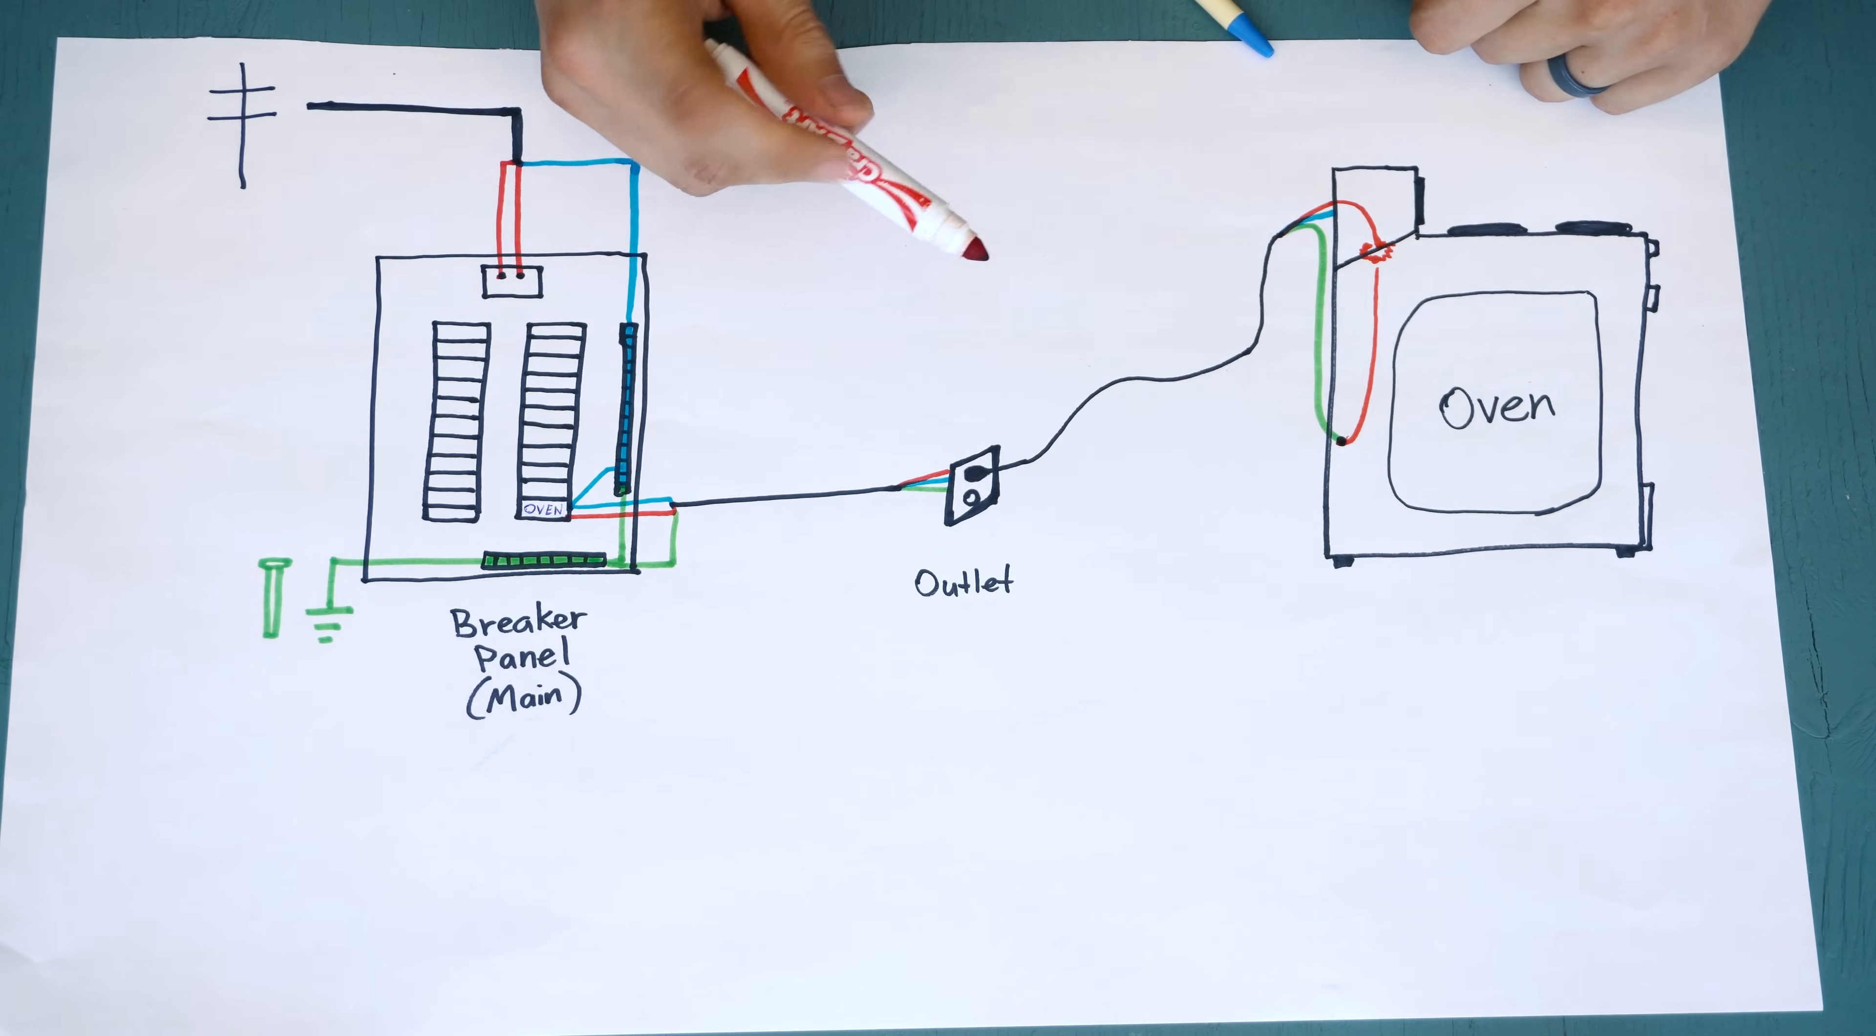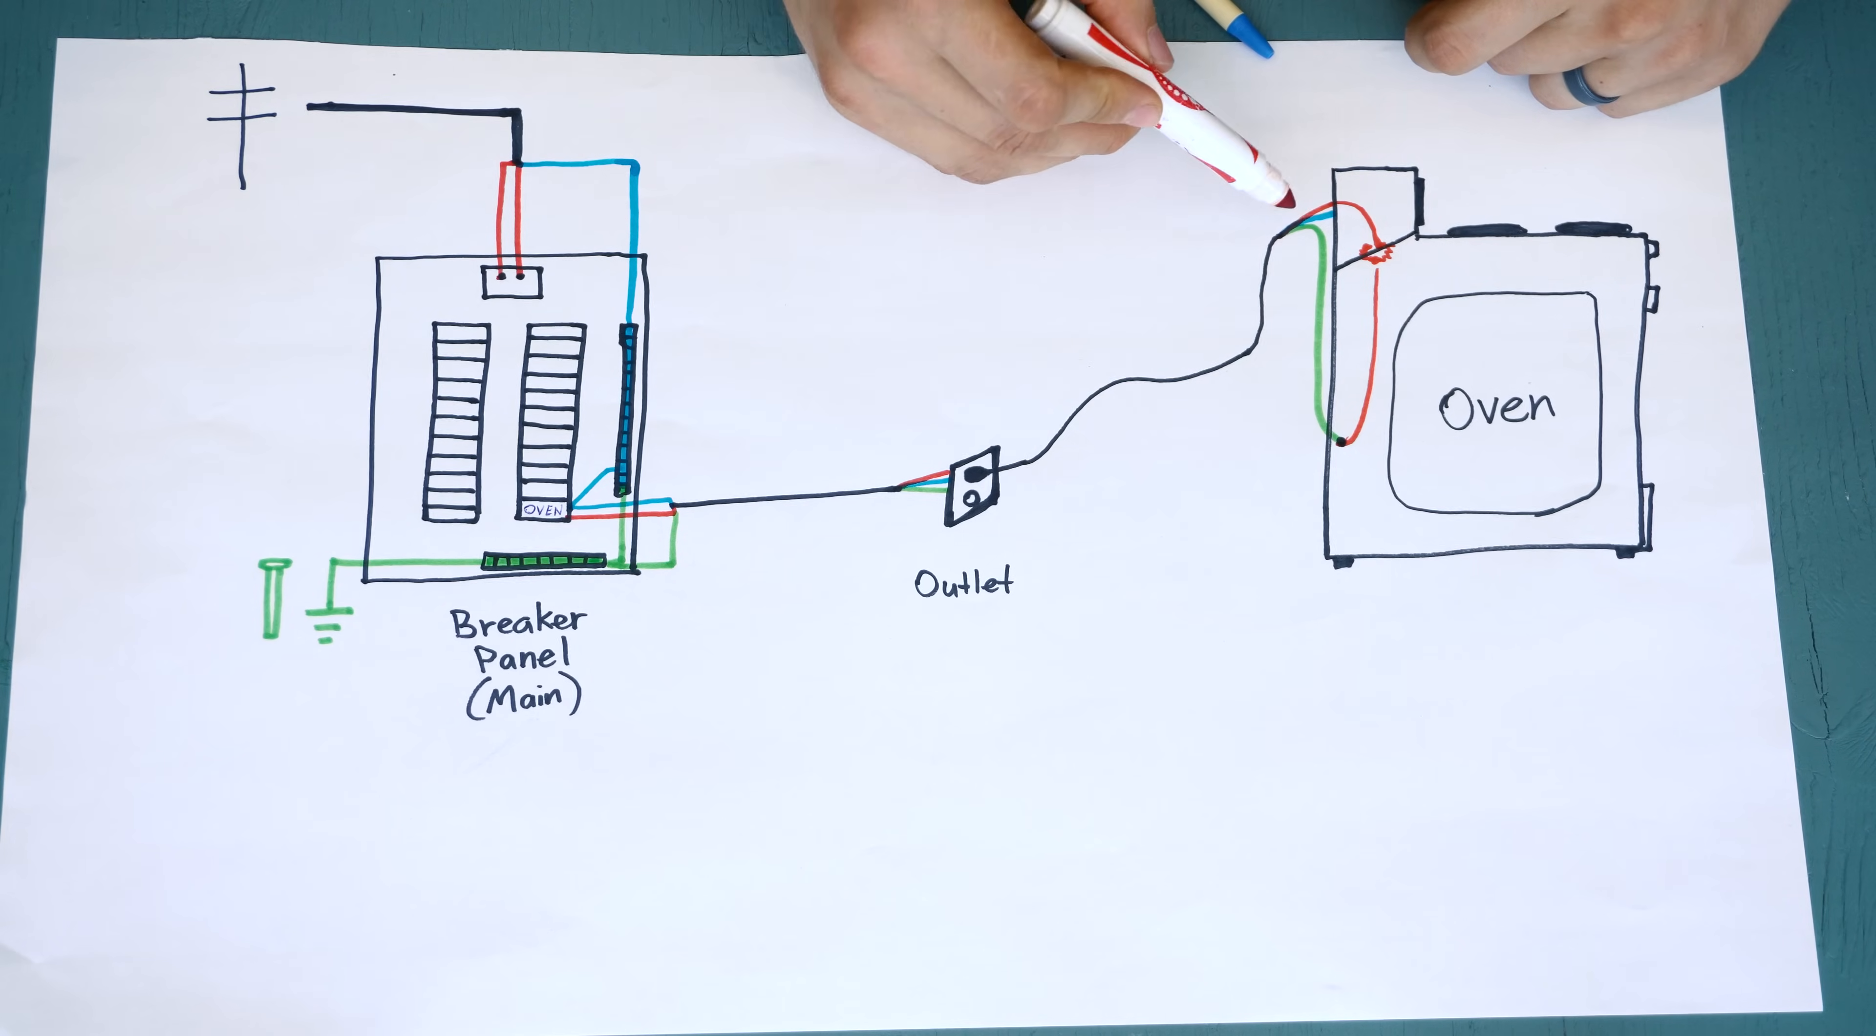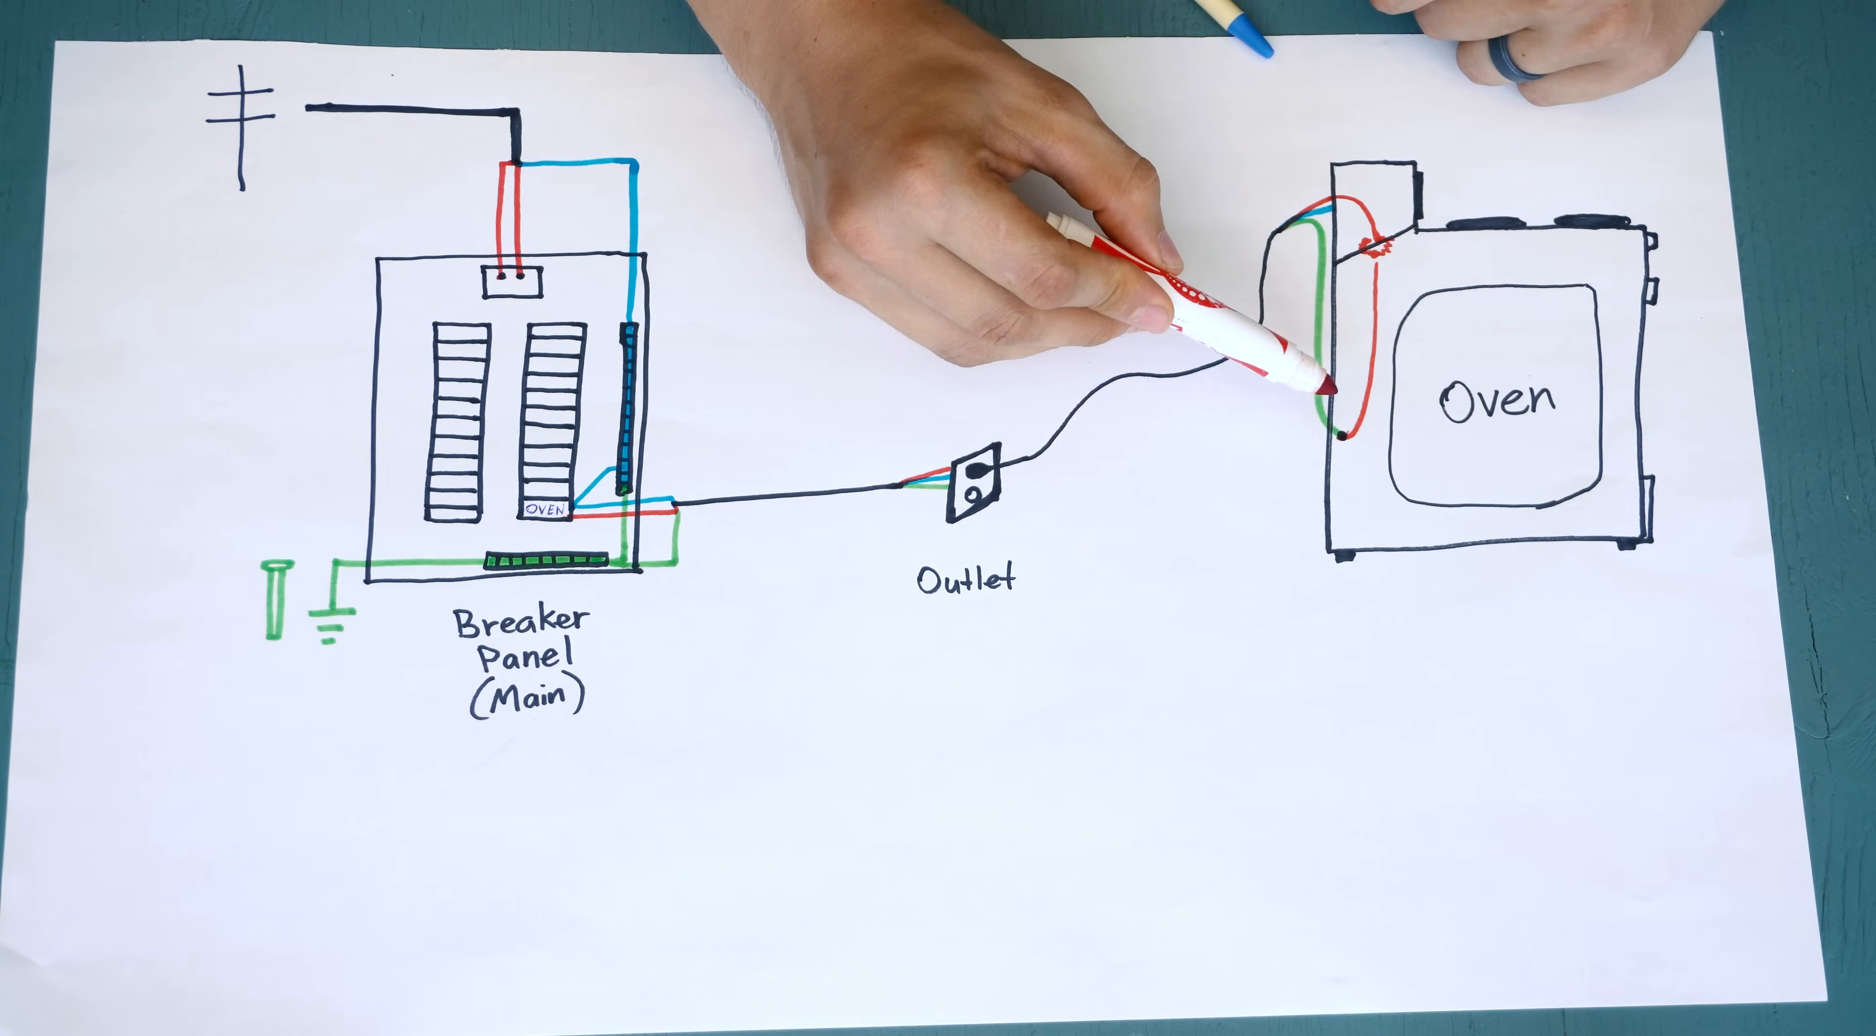And the frequent question people get is, can I use a ground as a neutral? And the answer is yes. Yes, but you really shouldn't, because the ground is a safety. So for example, you could disconnect this blue wire, or the white wire, the common, and instead hook up the green wire, and the appliance would work. But you effectively just removed that safety feature.